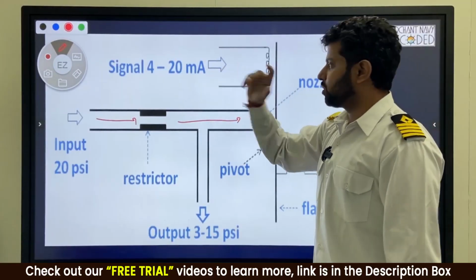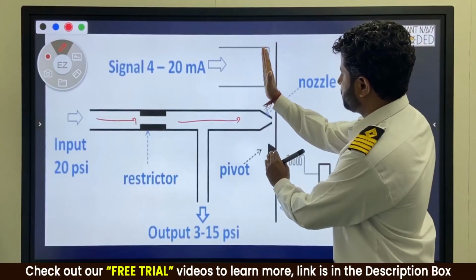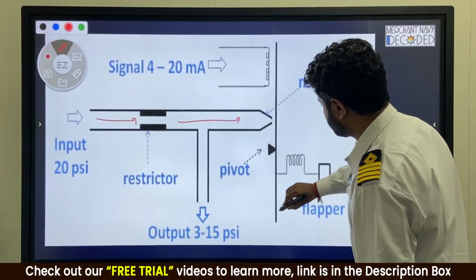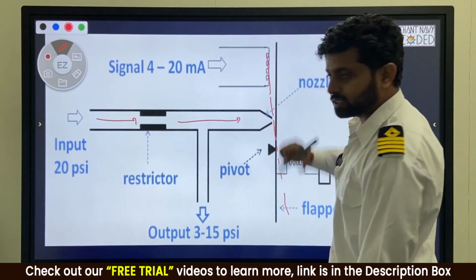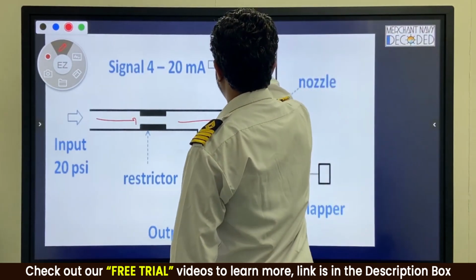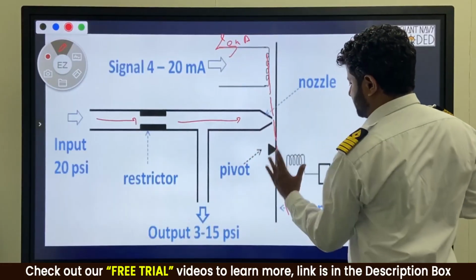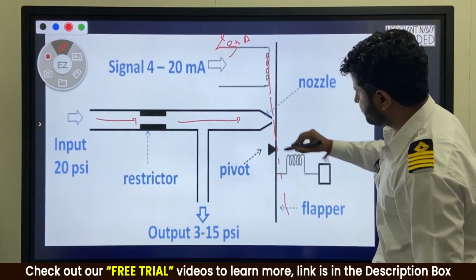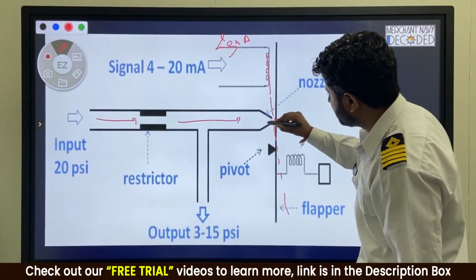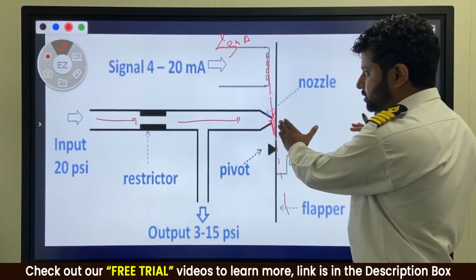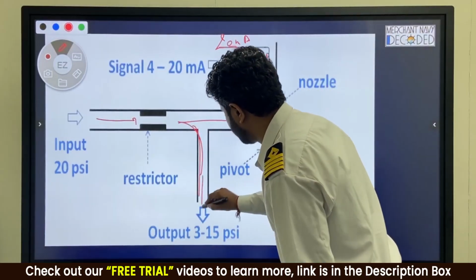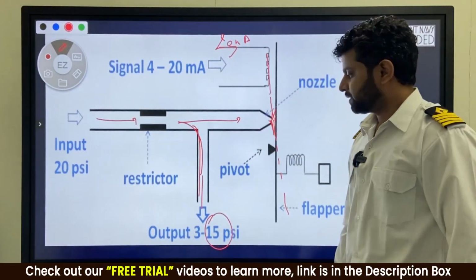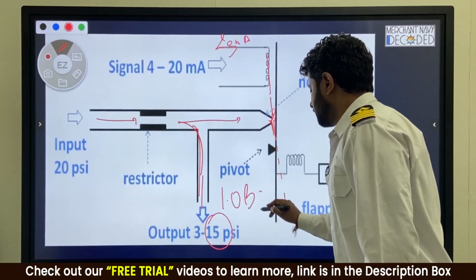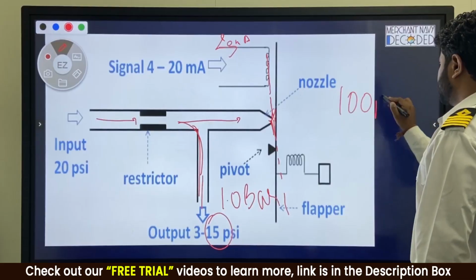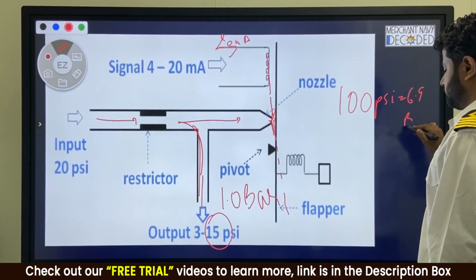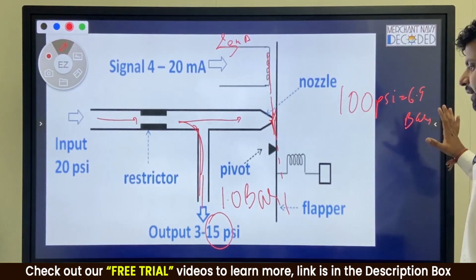Now if the current is more, maybe it will try to bring the nozzle towards itself, so the shape will become something like this. So when the current is 20 milliamps, it will try to pull this flapper nozzle towards itself, and it will become like this, due to which the amount of air which was going through it will reduce, and the maximum amount of air will go over here, which will be again 15 psi maximum, which is around 1 bar. For those who don't know, 100 psi is equal to 6.9 bars. Copied, guys? So 100 psi is 6.9 bar, you know that.